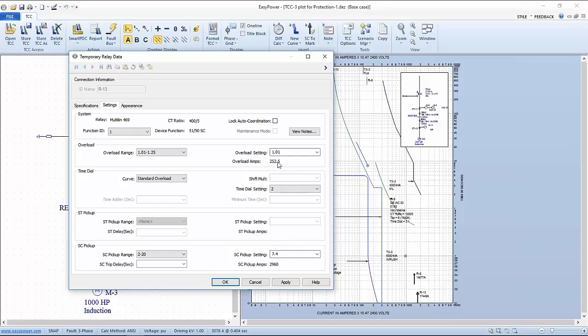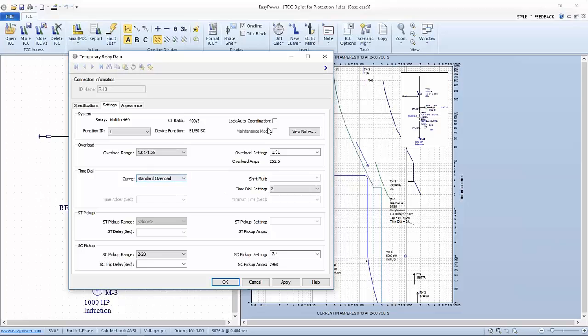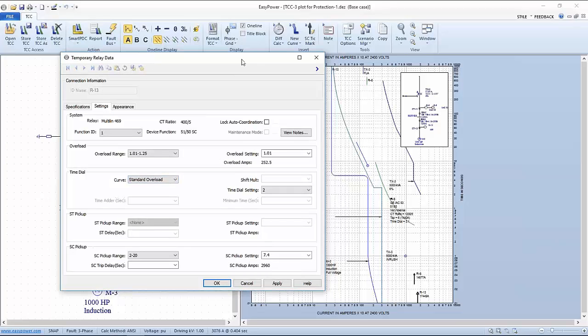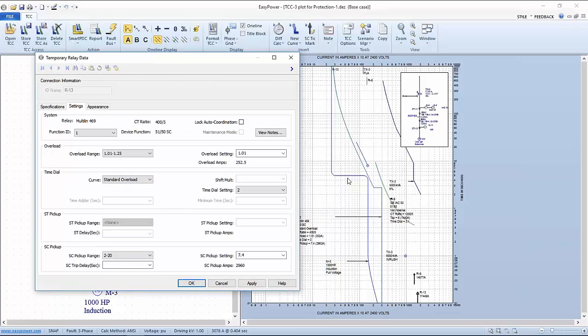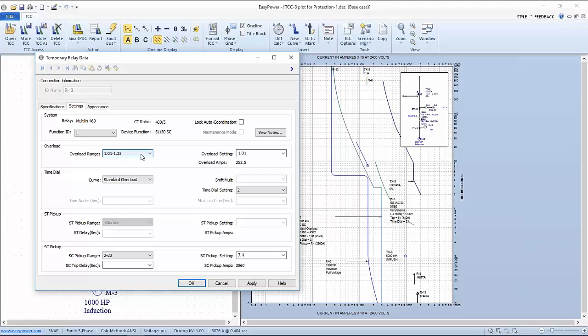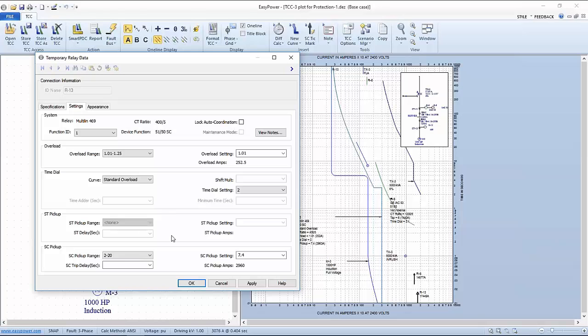The advantage of EasyPower's coordination module is that we can do this across voltages, different voltages and across different elements. For instance, if we were to plot this motor, these relays and these breakers, we can see that all those curves show up. As we expand this a little bit, we recognize the thin blue line is the motor starting curve. The more complex line is the relay that's a Multilin, and if we double click on it, which will actually be R13 inline with the motor. If we double click on it, you can see that it very nicely protects the motor from any spikes beyond a normal start and still does not allow anything to approach the thermal limit curve.